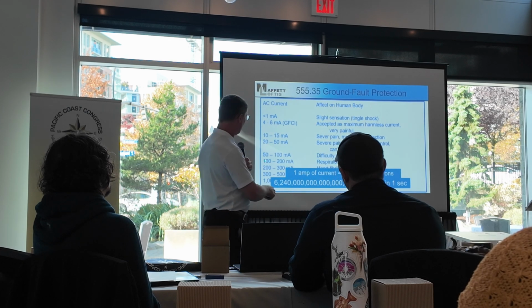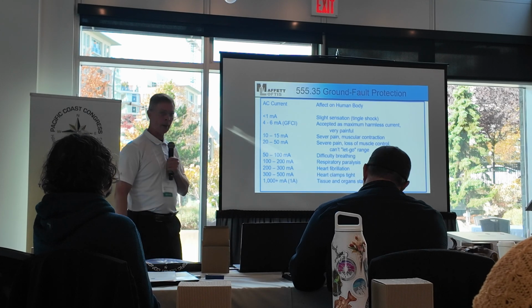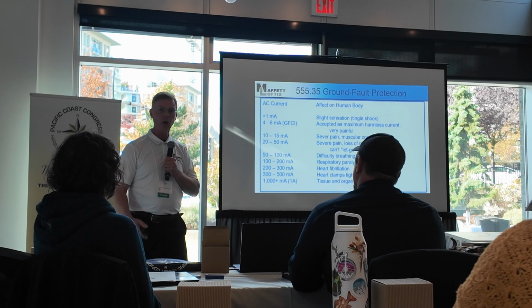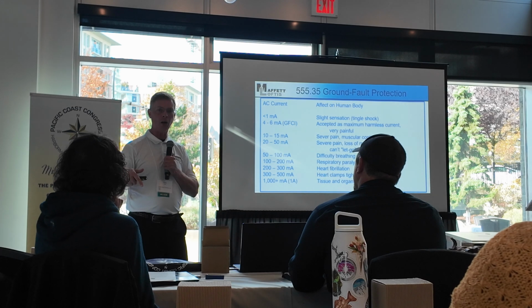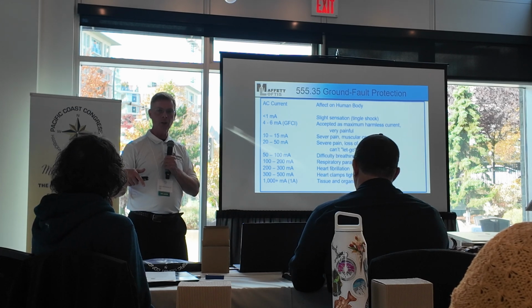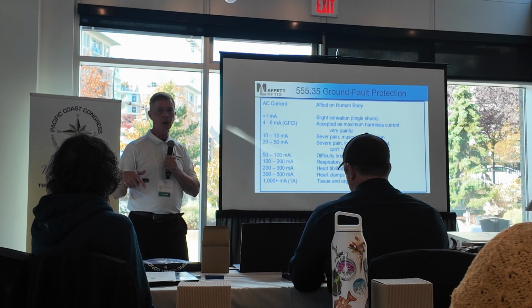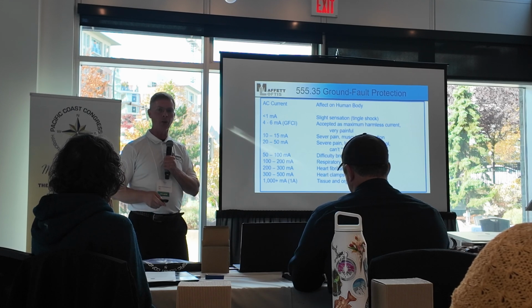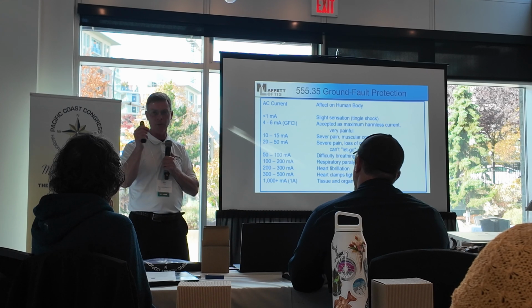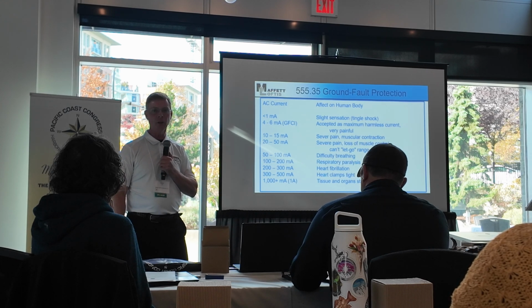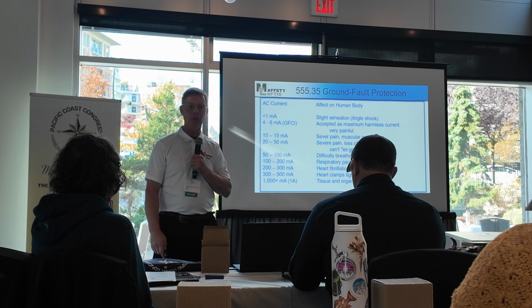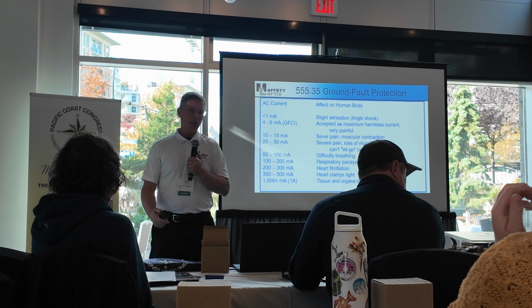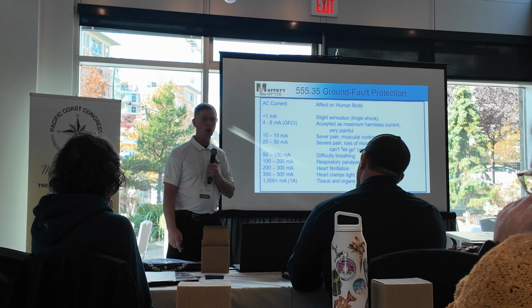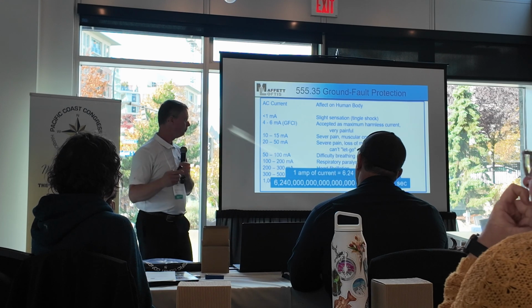And you think about that, is that dangerous? Absolutely. And this would not detect it. I called the engineer while I was on the call, found his number, and he says, "No, you're testing it wrong." I said, "No, sir, I'm not." And they wound up, and they had about 80 of these units installed on this one lake, and they had to fix everything. I actually pulled resistors and capacitors off their circuit boards and actually fixed it. And I never did go back and retest it. But to me, I'd rather have the true GFPE per code. Yeah, because that can't lie. It is what it is.